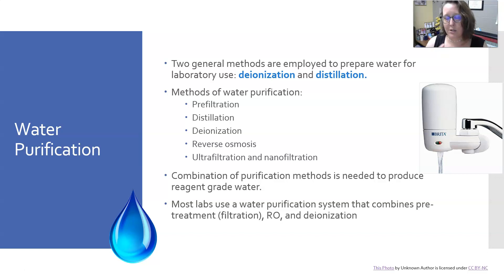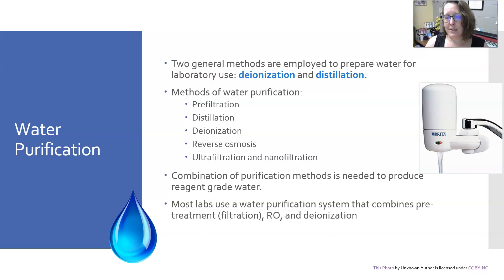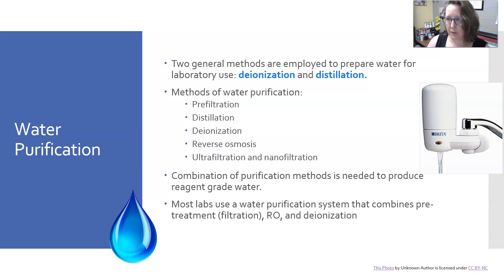Most labs use a purchased water purification system that combines a pretreatment — usually some form of filtration — then a reverse osmosis step, a deionization step, and sometimes an additional final filtration or ultrafiltration step, depending on what is needed.